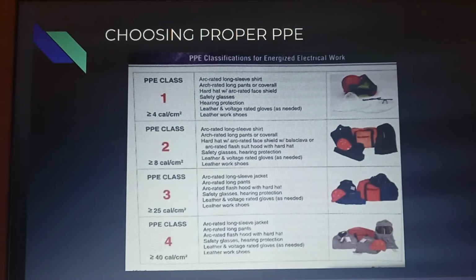So this next slide is choosing the proper PPE, and I guess I should just break it down a little bit by little bit. So class 1 is 4 cal/cm², and then class 2 goes 8 and more cal/cm², and then class 3 is 25 cal/cm² and above, and then class 4 is 40 cal/cm² and above. So class 1 is like an arc rated long sleeve shirt, arc rated long pants or overalls, hard hat with arc rated face shield, safety glasses, hearing protection, leather and voltage rated gloves as needed, and leather work shoes. That's just one of the classes. I'm not going to read all of them.